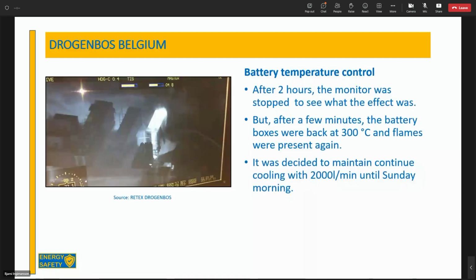After two hours with full power, 2,000 liters per minute, they stopped to see what was happening. But after a few minutes, the battery boxes were back at 300 degrees Celsius and the flames returned. So remember what I said: this is like a roof where water runs off like drains, it cannot reach cell level. This is a problem, and it's also why Perola showed you the Cobra system and the Muir system, because we need to reach cell level to extinguish, or let it burn out.